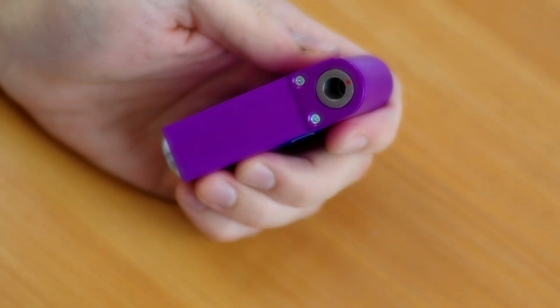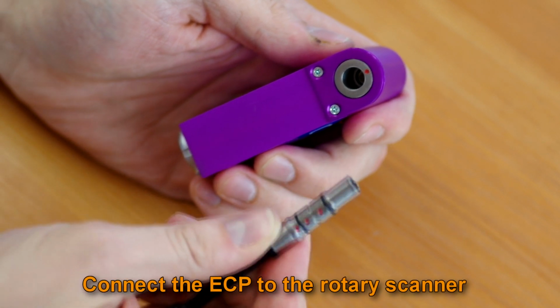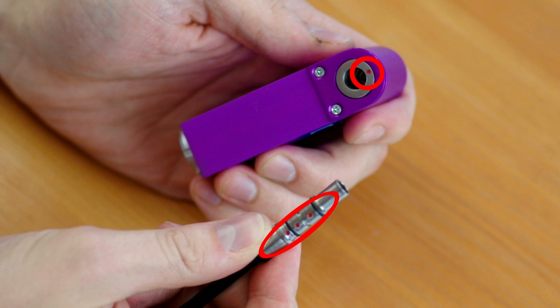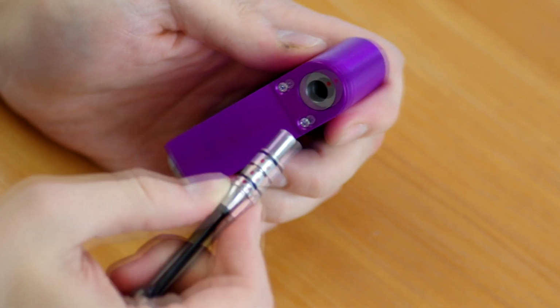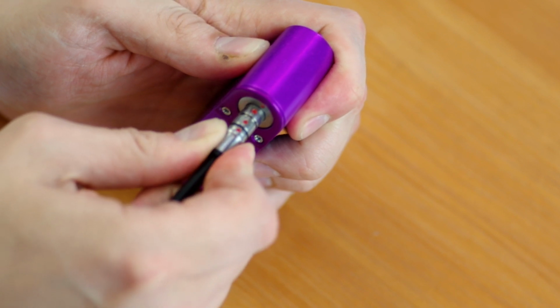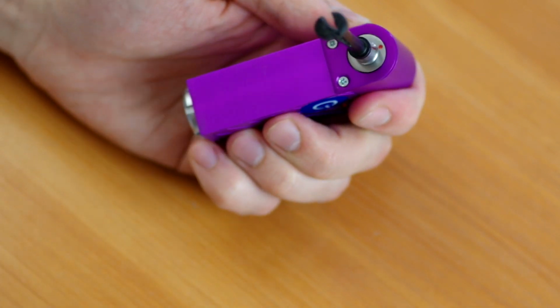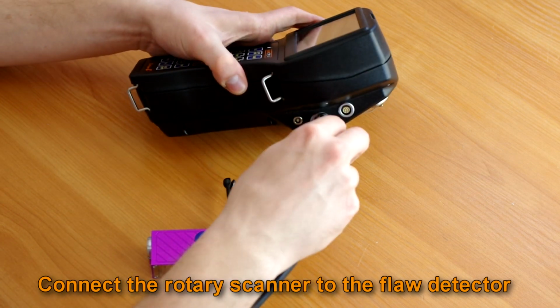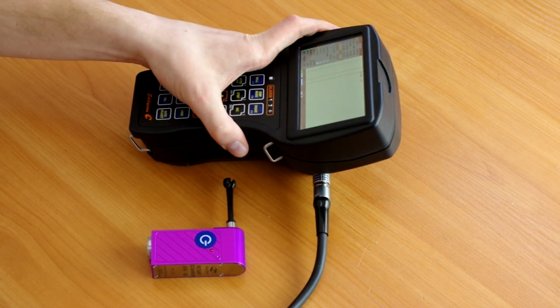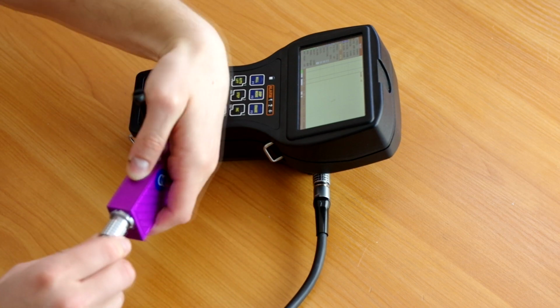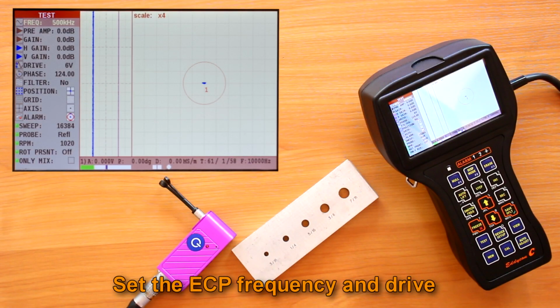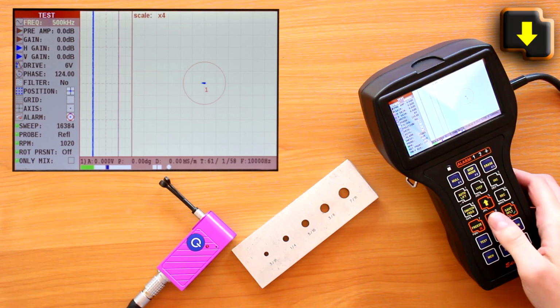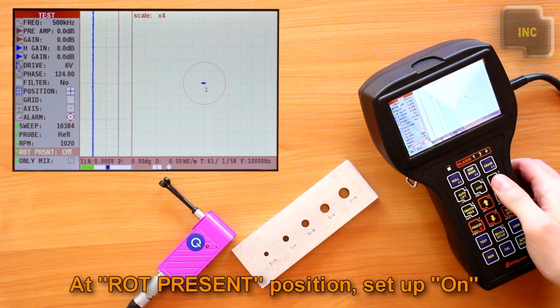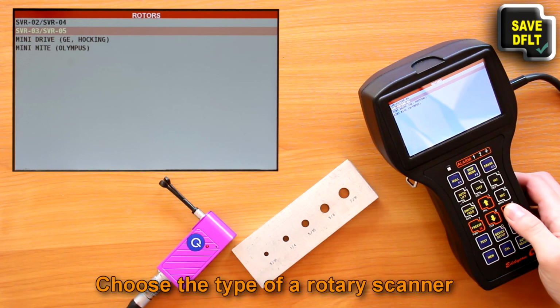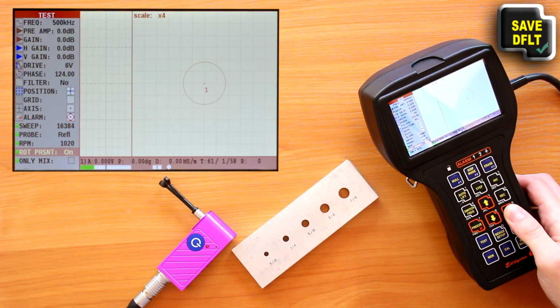Rotation probe. Connect the ECP to the rotary scanner. Markings on the housing of the probe and scanner should coincide. Insert the ECP in the scanner without applying excessive force. Connect the rotary scanner to the flaw detector using a connecting cable. Set the ECP frequency and drive in a range specified in the registration certificate of the ECP. At rot present position, set up on. Now choose the type of a rotary scanner and press the Save Default key.